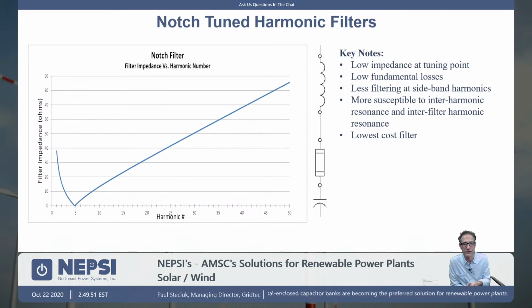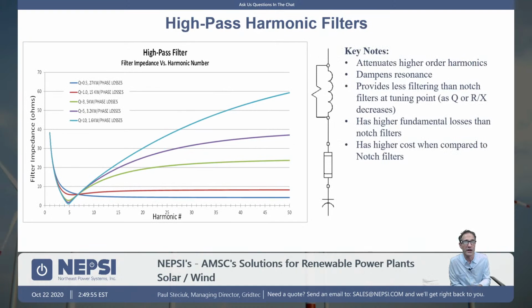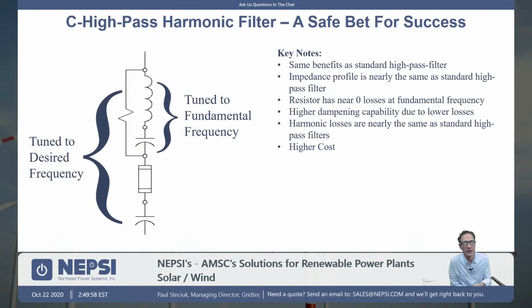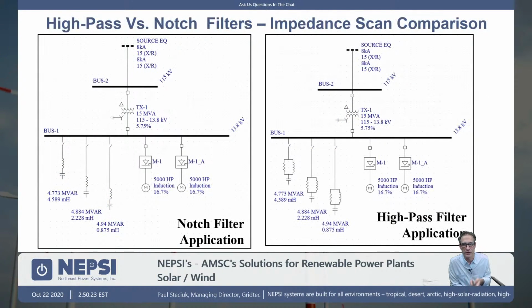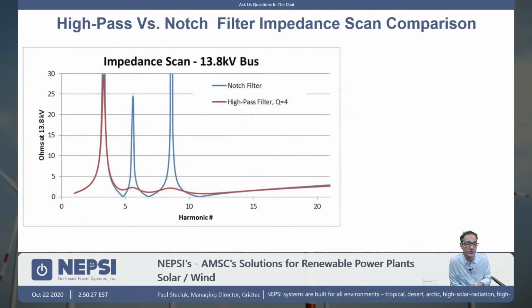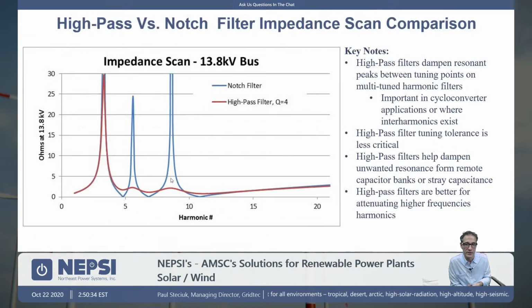We've got other tech talks that talk about filters and types of filters, but we can convert that to a notch filter, a high-pass filter, and a C high-pass filter. Most oftentimes when you do have a resonance issue within a renewables plant, we're pushing to a C high-pass filter. And like we did in the initial slides in the beginning of this presentation, you can get a very significant damping factor within the filter, and we can eliminate resonance concerns associated with capacitor banks and even the collector system cables. Really here we're just showing slides. The difference between notch filters and high-pass filters is the elimination of the resonant points that you get between notch filters and damped filters. So C high-pass filters and high-pass filters eliminate the resonant points that exist below the tuning point of a notch filter.